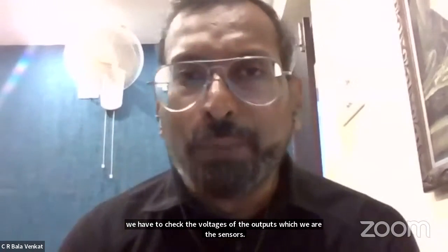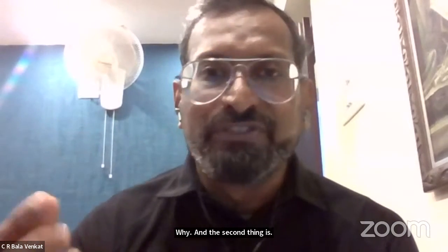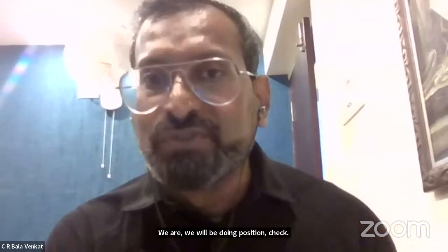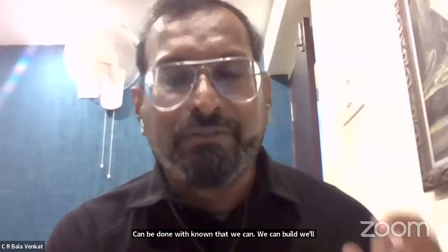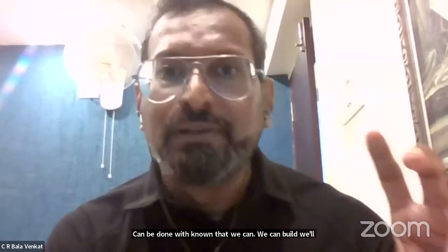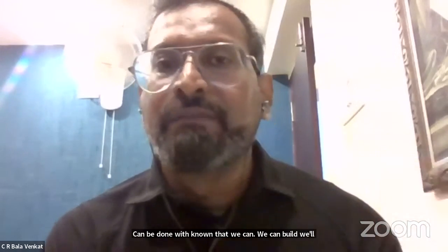Why? And the second thing is the probes. For the probes, we will be doing a precision check. A precision check can be done with a known absorbance, for which we will run potassium dichromate, a traceable material which is available.